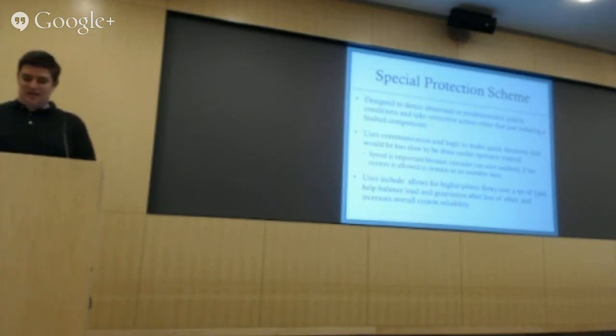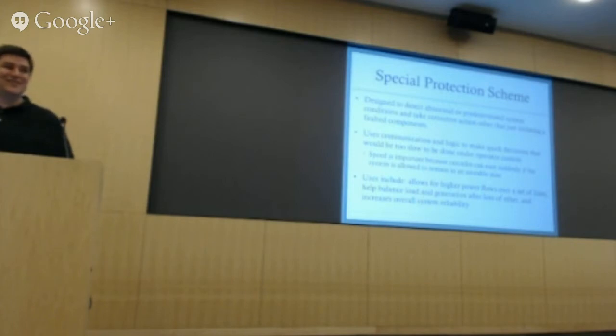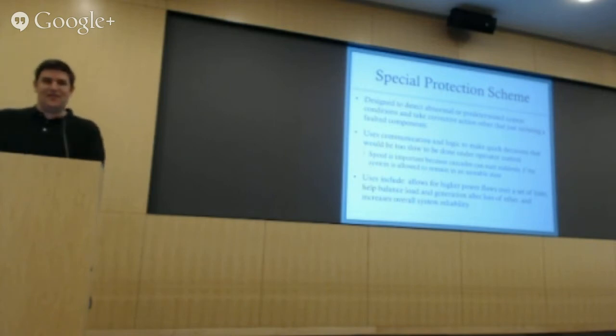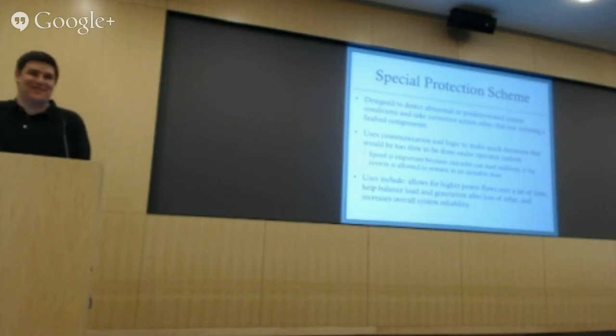Yeah. Well, a lot of the DC is usually used like the one that runs from Oregon all the way down to LA is 500,000 plus and 500,000 minus, so it's 1,000,000 volts technically, but it's centered ground, so that we don't need to have crazy insulators. So high voltage DC usually means really high voltage for that kind of stuff. Even the voltages for transmission lines go up to 500,000 volts, 230,000 volts. It's all about reducing the current, so you can reduce the conductor size. There are lines that run 1,000 amps normally. So yeah, it's quite humbling when you see the actual figures of some of this power.